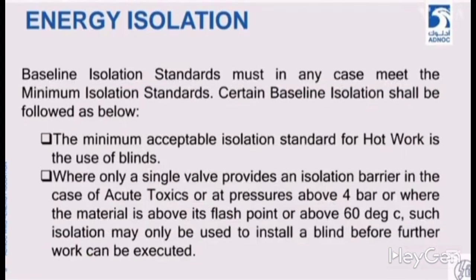For any task, we must fulfill the minimum isolation standard. Under what conditions? For example, the minimum acceptable isolation standard for hot work and blinds. If we are to perform hot work on any active service line or any equipment, we will not accept single isolation for it. We must meet the baseline isolation standard there. It is mandatory to do so where only a single valve is provided in the isolation barrier. If there is any place where there is a single valve, then this will be a barrier.